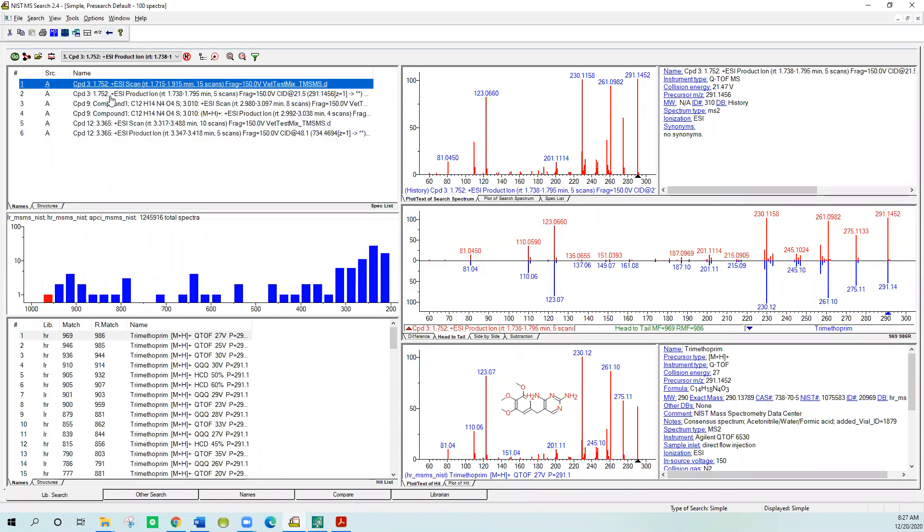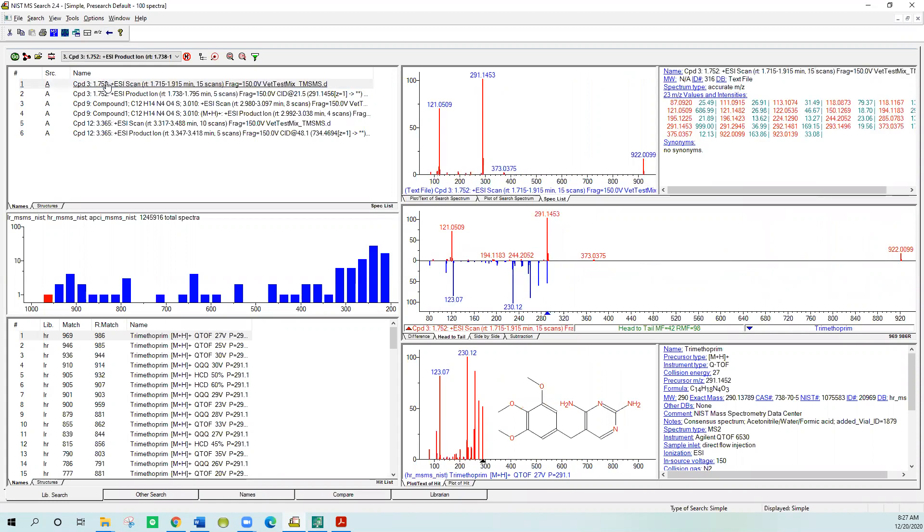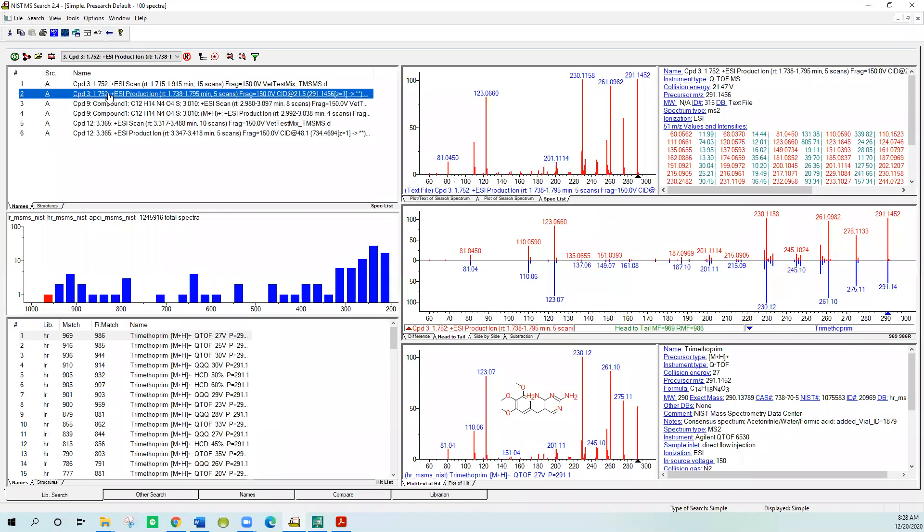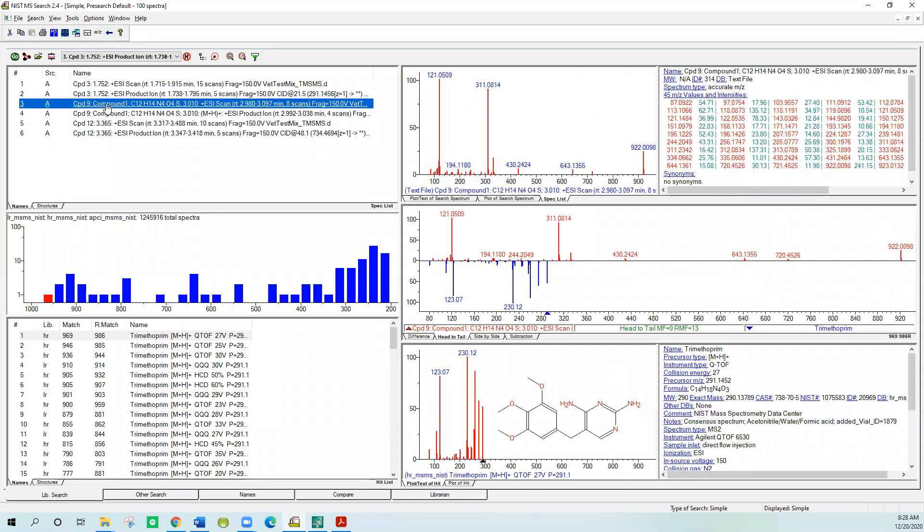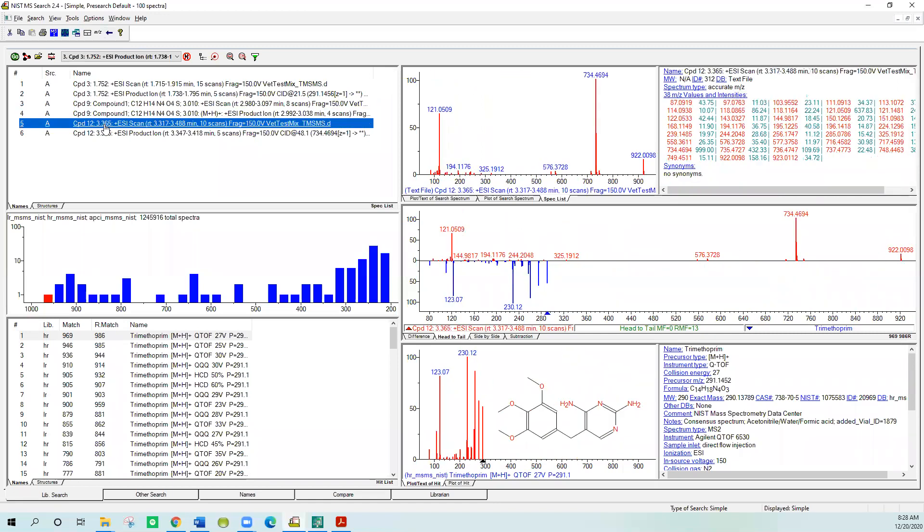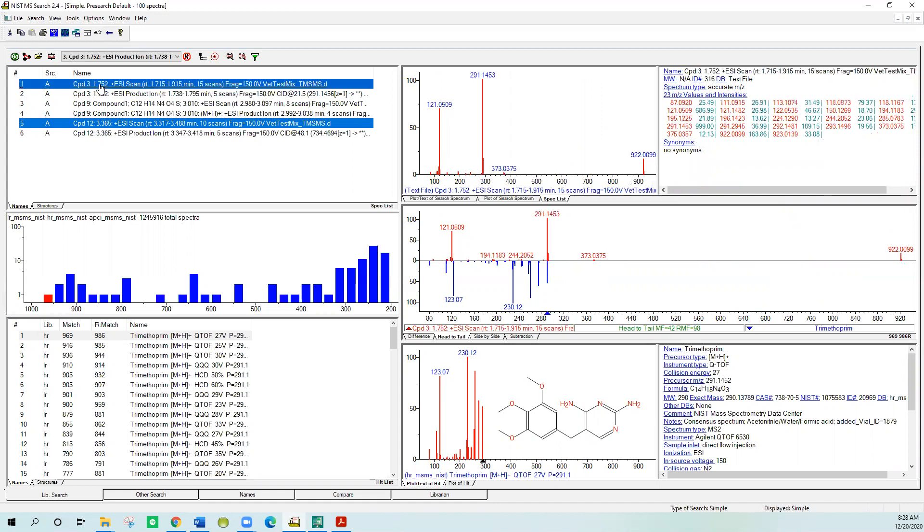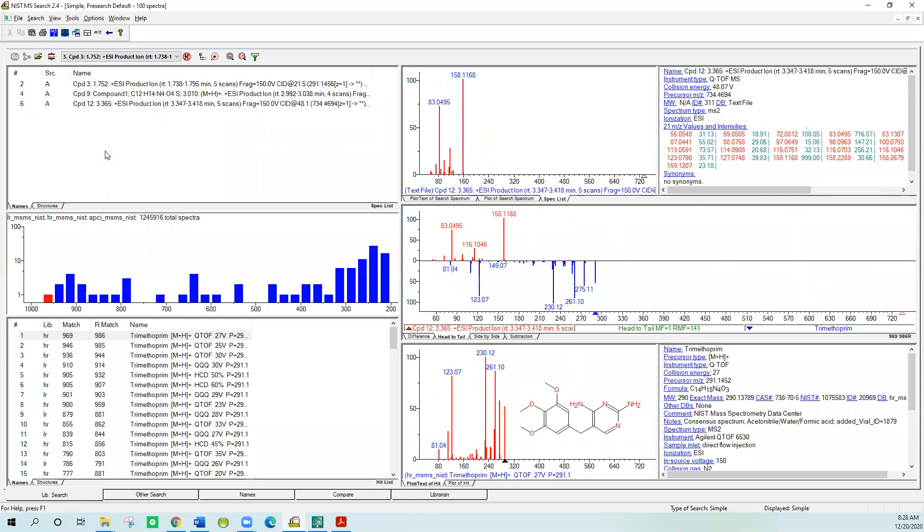Here I didn't tell it to do a search when it came in, because as I said before, this is the spectrum from the Agilent software. It has the lock masses still present, so I'm not interested in seeing those. I'll get rid of those. The first one in every one. So this is compound three, it has the second one will be the MS-MS, and for nine the first one will be the lock mass again, etc. for compound twelve. So I'm going to hold the control key again, and I will select three, the first one for nine and twelve, and those are the ones that have the lock mass. Now I've selected them all and I can right-click on my mouse and say cut. So I've kind of cleaned it up just to clean it up a little bit so I'm not looking at all the rest of them.